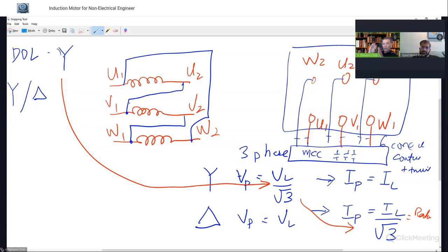For example, if other motors are running, when you have a voltage dip, then the current will increase because the running motors need the power to maintain their process parameters. So when it goes up in current, then further voltage drop will occur. Then it may cause a total power failure. So those are the studies that electrical engineers need to do to decide whether we are going to go for the simple method DOL, very cheap, very easy, or we go for a little bit higher solutions, star delta or auto transformer, or in fact, if a process needs it, then we may go for VFD.